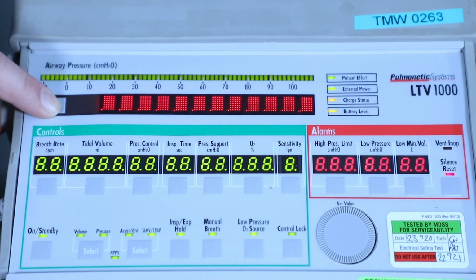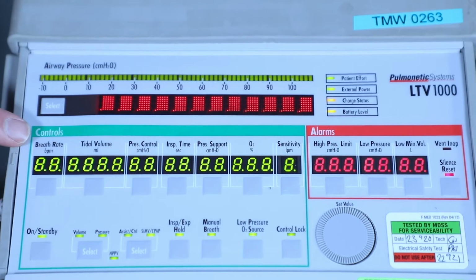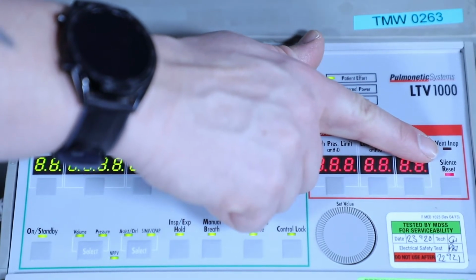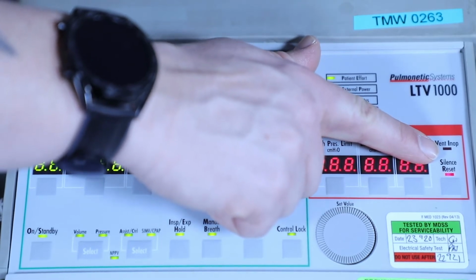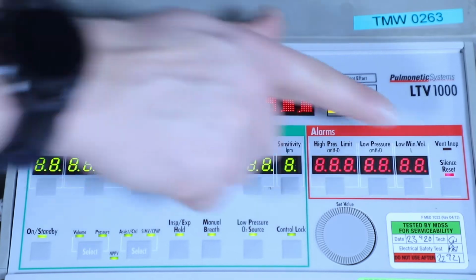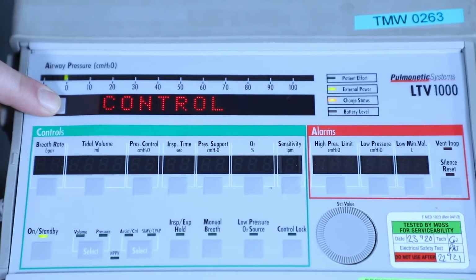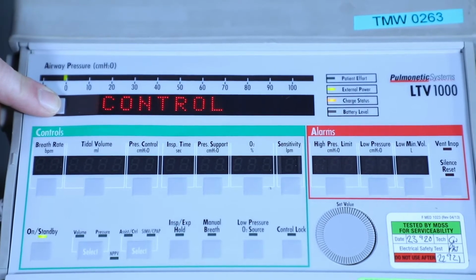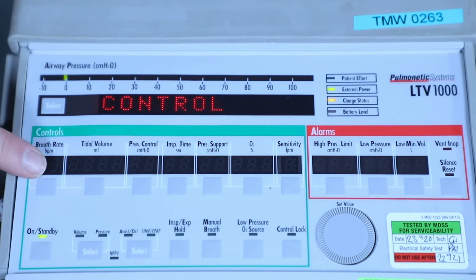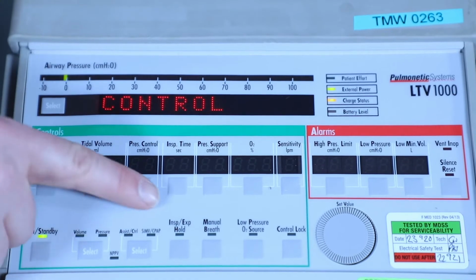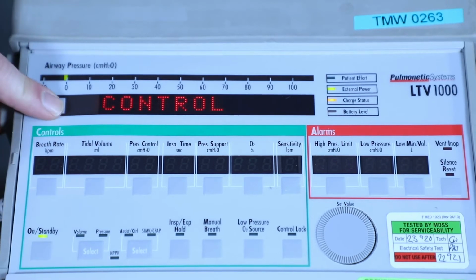Pressing the select, you can see that every LED on the ventilator lights up, excluding the vent in-op, which should only light up when the device has been switched off whilst the ventilator is operating. Press the select button to move to the next menu. As the control, here we're going to check each of the device buttons to ensure that they relate on screen to what they say above and below.